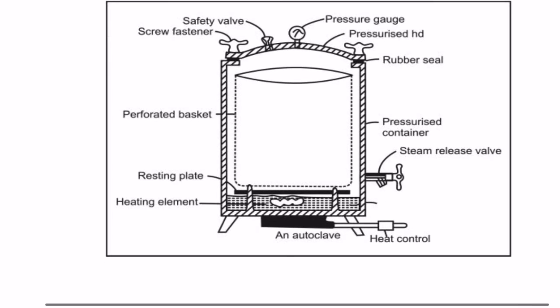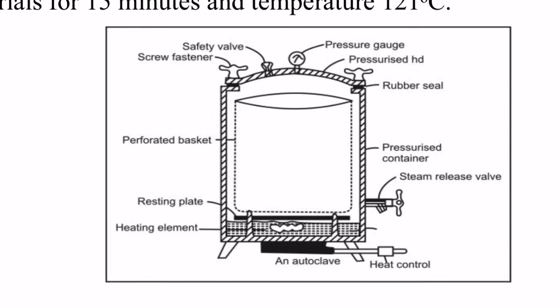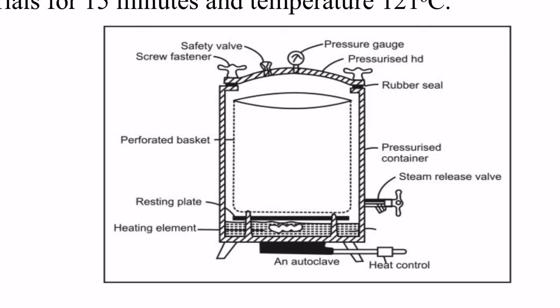This is a diagram of the autoclave. In the autoclave there are knobs — you can see the upper knobs which are named screw fasteners. There is also a safety valve, pressure gauge, pressurized hood, and rubber seal. The rubber seal attaches the container to the upper lid. This is the autoclave lid.